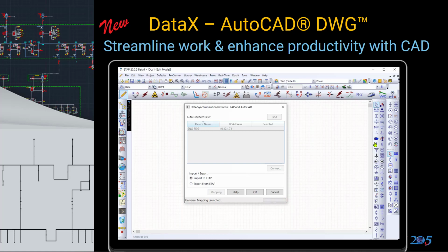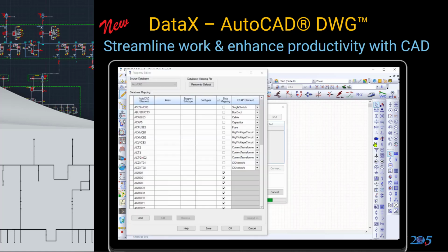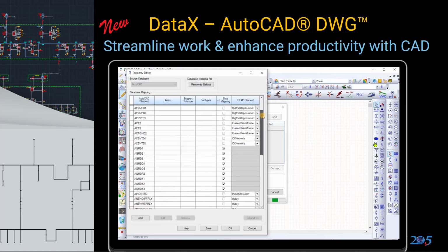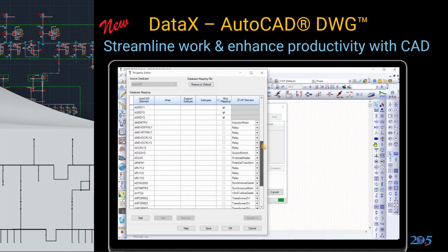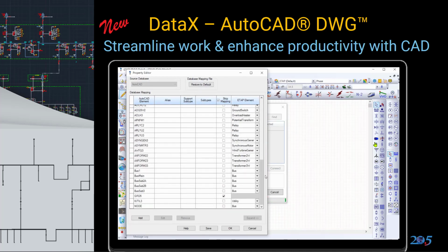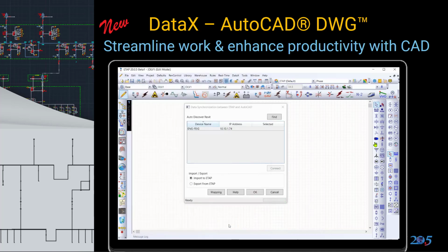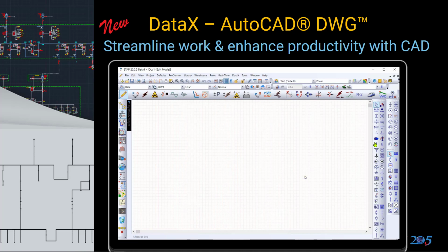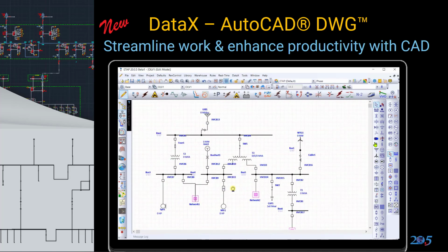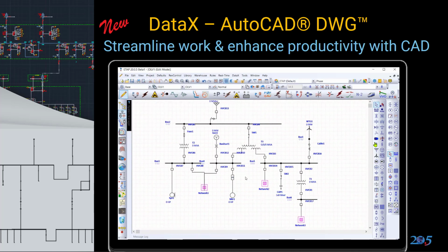We can then go ahead and click on the mapping file, which essentially helps us compare the AutoCAD elements with the ETAP mapped elements. We've already done the hard work of pre-mapping a lot of these components over to ETAP, but in case any of these components are not mapped or correctly mapped, you can adjust the mapping for your system and then import the file directly into ETAP.